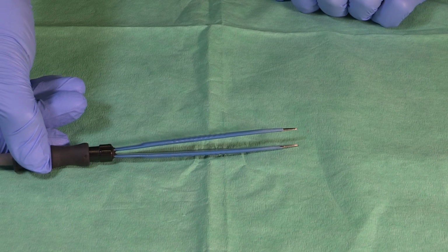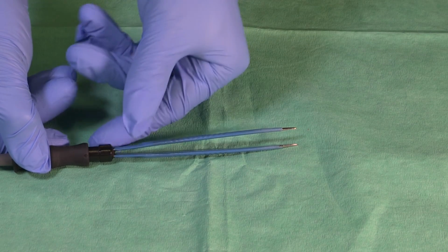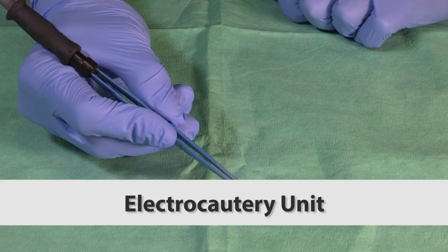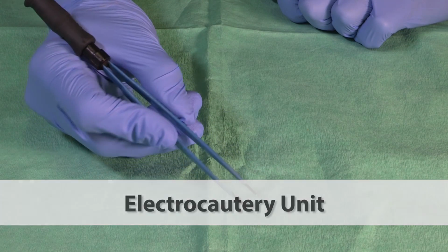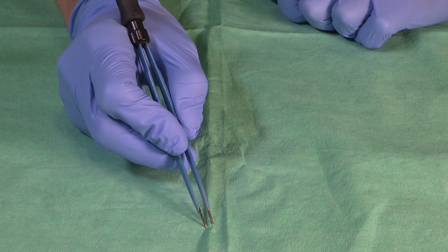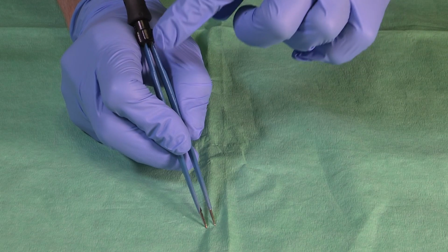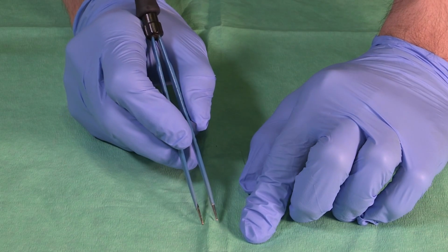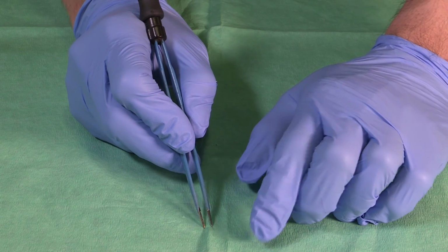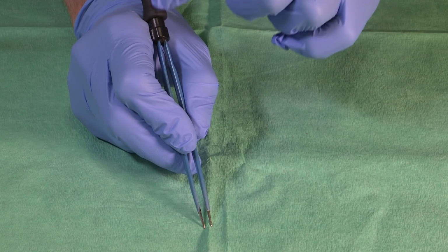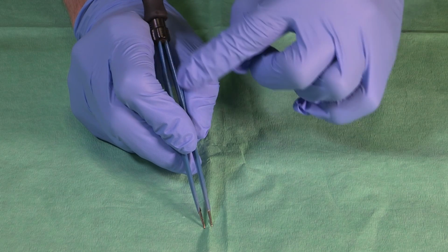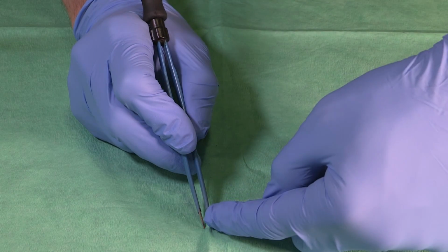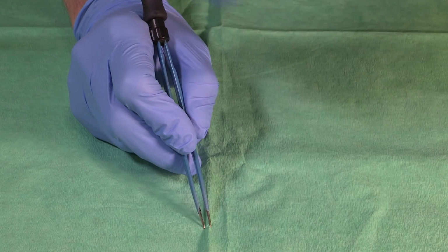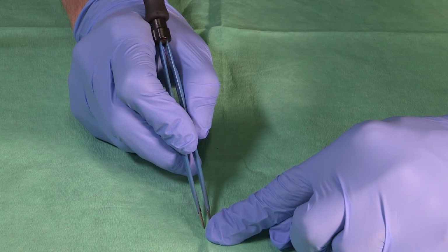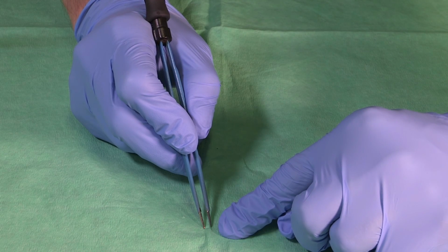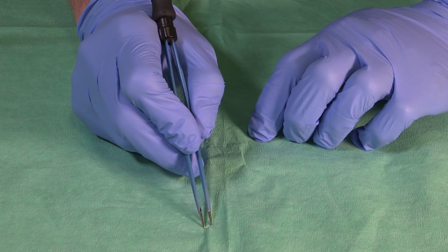So we'll take a closer look at the electrocautery unit that we have here. This is a bipolar electrocautery unit. You can see it has a handpiece which is very similar to a pair of thumb forceps or tissue forceps, and it's designed for just picking up tissue between the jaws. And what will happen is if you've got a bleeding vessel or something of that nature you want to cauterize, you can just gently grasp the tip of the vessel between the blades of the handpiece here. And when you fire the device, which you do using a foot pedal, an electric current is passed down one blade, passes across between the two jaws, and returns back to the unit through the other blade. And what that does is focus that electric current through the tissues between the jaws of your handpiece, generates heat, coagulates protein, and achieves hemostasis at that point.